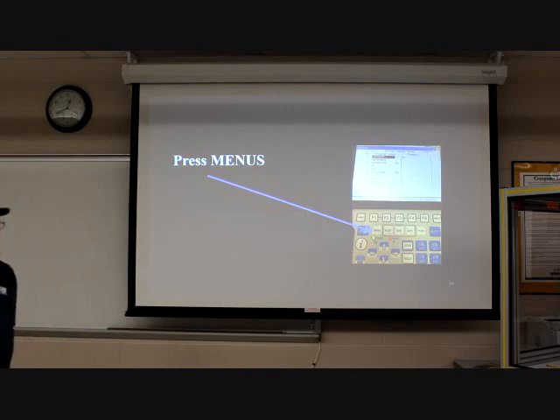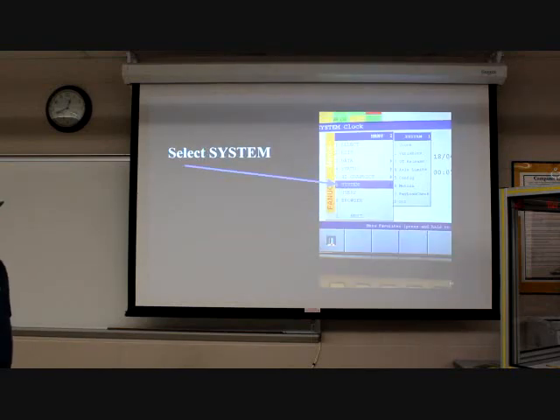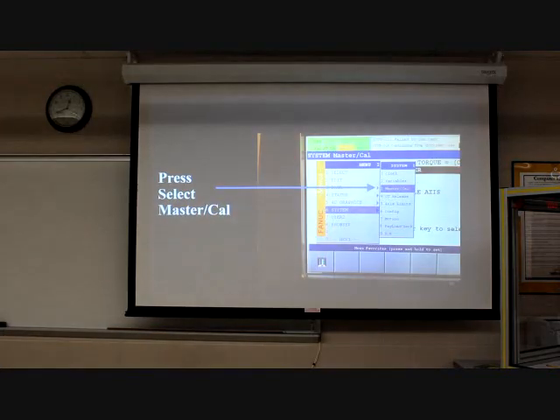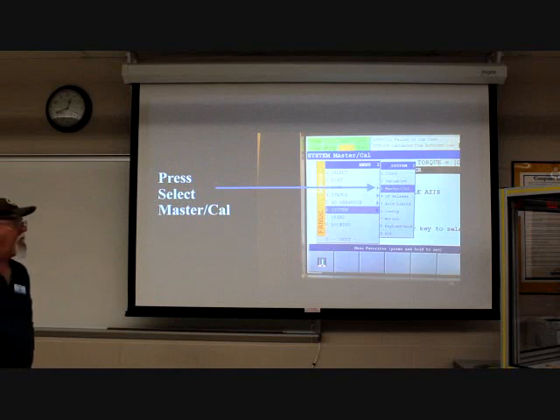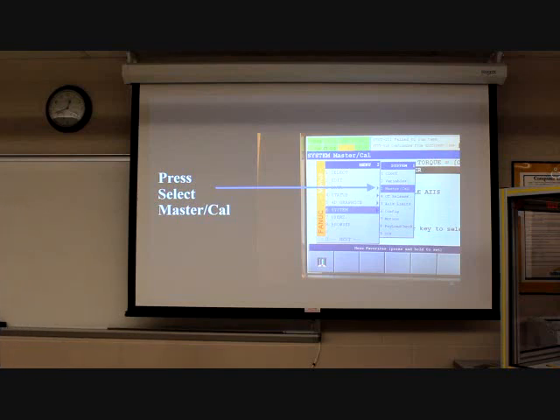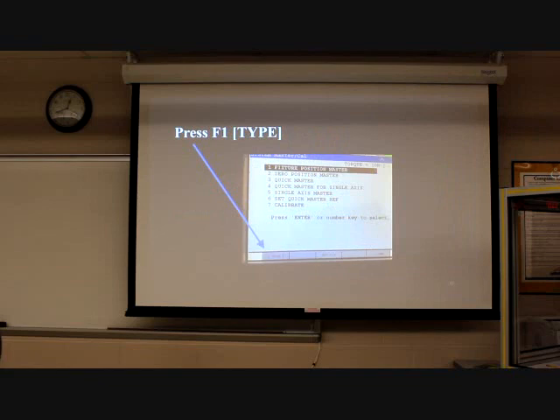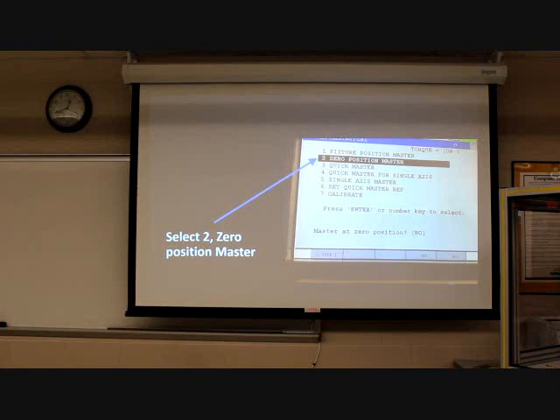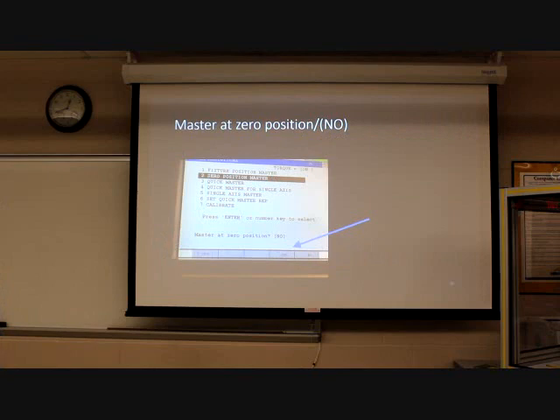So once I have everything lined up on all my witness marks, double check everything, make sure they look good, then I'll press Menus. I'll find the System tab. Since we went through and enabled the master calibration function previously, it's now showing up under the System tab. We'll press Master Calibration. We'll click on Type, F1. As you see here, it gives us, again, all our options for mastering. We're going to select 2, zero position master. See, master at zero position, no on the screen. We're going to click on yes.